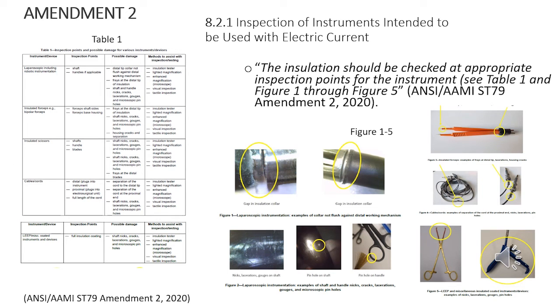AAMI goes on to state that insulation should be checked at appropriate inspection points for the instrument. See Table 1. What's really nice is that on the far left, Table 1 lists the instrument and device to be inspected, for example laparoscopic including robotic, insulated forceps, bipolar forceps, insulated scissors, cables and cords, and even LEEP instruments. The next column lists inspection points, and some examples would be the shaft, the forceps shaft sides, the handles, the blades, and also the full instrument itself.